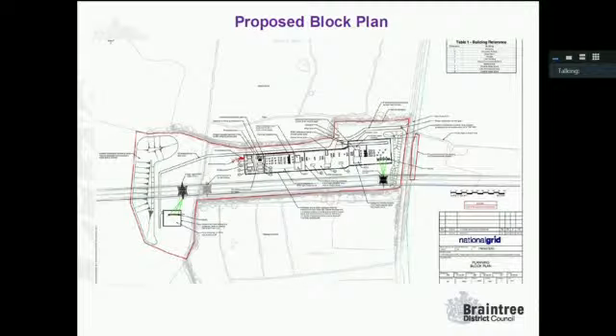Access into the site is proposed off the A131 at this location, with a field gate at the entrance. There are two supergrid transformers proposed, each with a noise enclosure around it to reduce operational noise - one and two. The electrical equipment within the substation would typically be 9 metres high above ground, with a 13 metre high steel landing gantry structure supporting the down leads from the adjacent existing 400 kilovolt overhead power line to the southeast, in this area here.